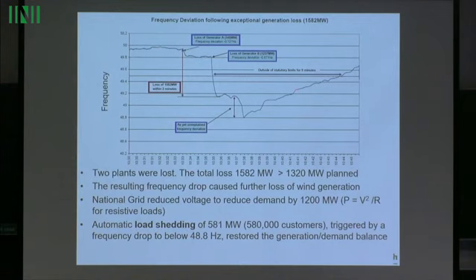but frequency was still dropping, and you see it dropped to 48.8 and then started to increase. This is because all power systems have so-called under-frequency automatic load shedding. And they have a number of stages. So when frequency drops in this country to 48.8, a number of loads will trip automatically because you need to protect the system. The only way you protect the system is to reduce the demand. There are usually 3 stages. So it'll be 48.8, then I can't remember, 48 something, etc. The main thing is to protect the system, so you have to trip some demand.